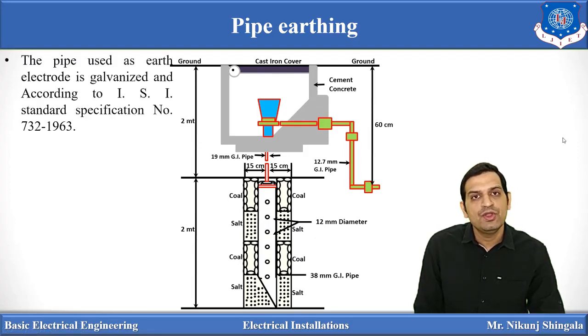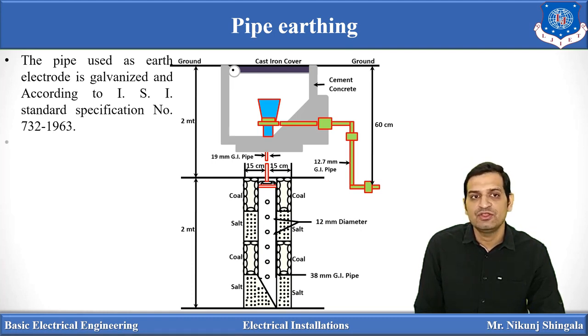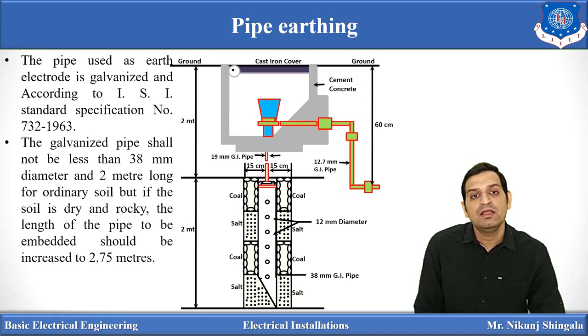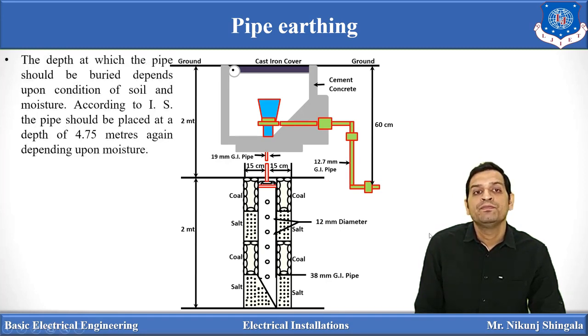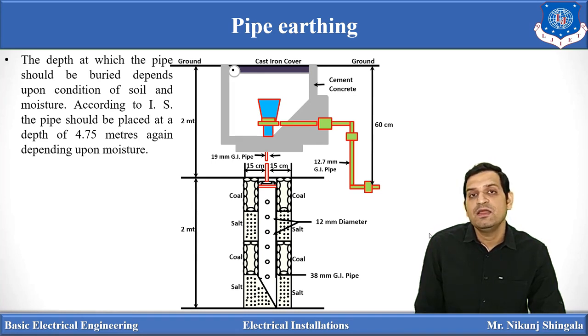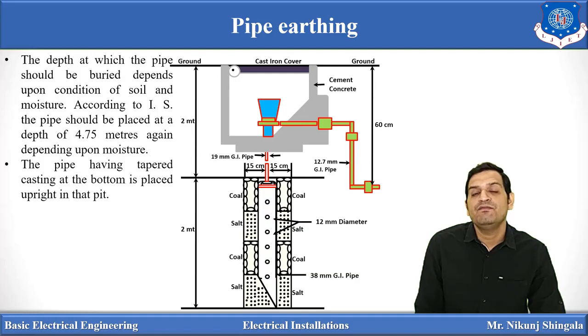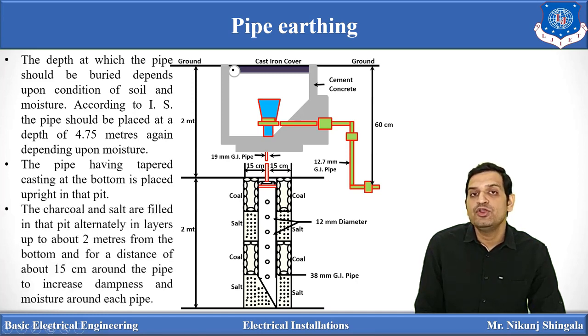Regarding the standards to be followed: the pipe used as an earth electrode should be of galvanized material per ISI standard 732-1963. The galvanized pipe should not be less than 38 mm diameter for ordinary soil, but if the soil is dry and rocky, the pipe length can be increased up to 2.75 meters. The depth at which the pipe is buried depends on soil conditions; per ISI standard, the pipe should be placed at 4.75 meters, depending on moisture. The pipe with tapered casting at the bottom is placed vertically in the pit. Charcoal and salt in alternating layers of 15 cm by 15 cm are filled around the galvanized iron pipe.